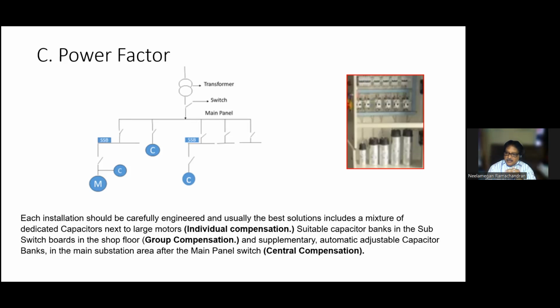Then another 20 to 30% should be in group compensation, which means it has to be in the SSB, the sub-switch boards, where you connect the capacitor. So when the SSB is switched on, the capacitor comes into play, and the power factor of the load connected in that SSB is maintained. And individual compensation means in the motor.